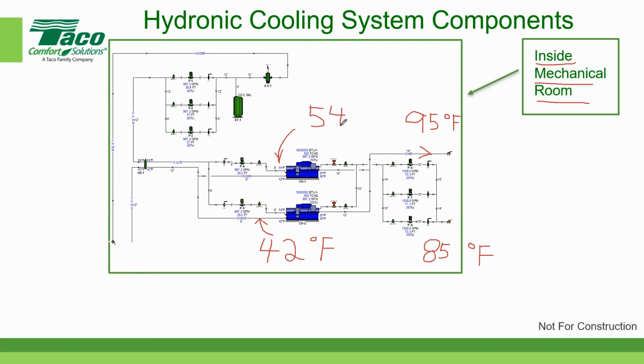So does anybody want to tell me what the difference in temperature is between the supply chilled water and the return chilled water? Anybody can do that high-level mathematics? They want to type that in. Let's see if we challenge some folks out there. See if they're still awake after being late at night. Well, some folks are late at night, others are earlier in the day, or maybe even very, very early. We've had a couple of type-ins. 12, a lot of 12s. 123. I'm not sure where the 23 came in, but I think he corrected himself. So the delta T on the chilled water side is equal to 12 degrees Fahrenheit.